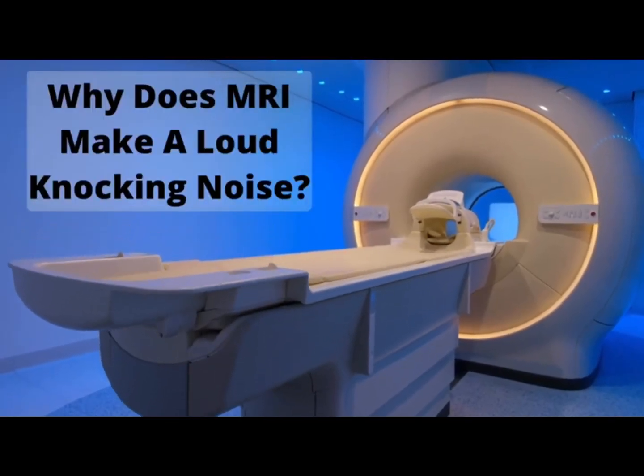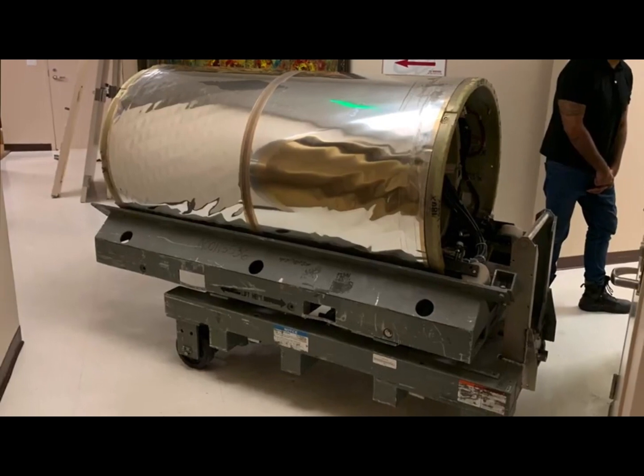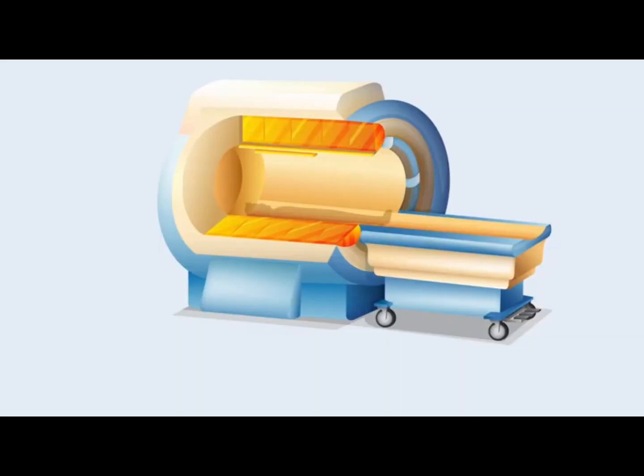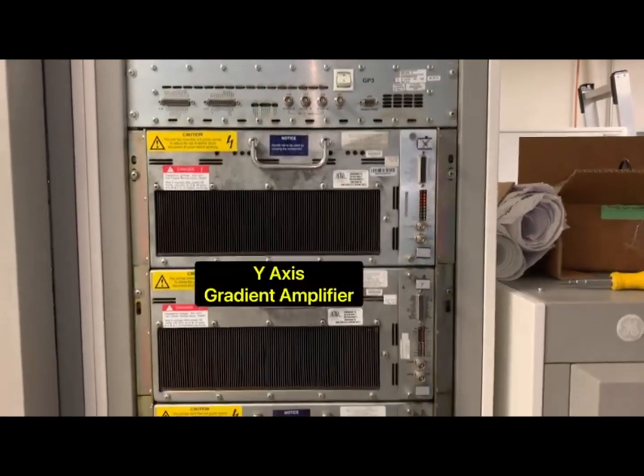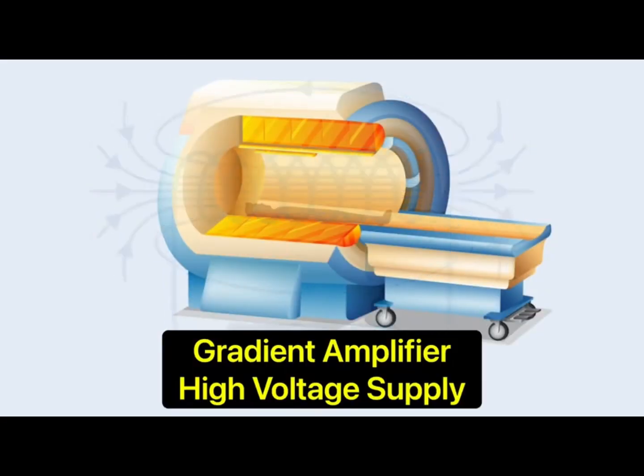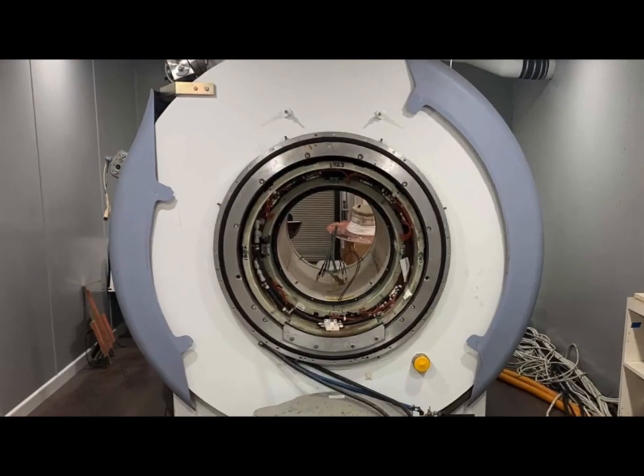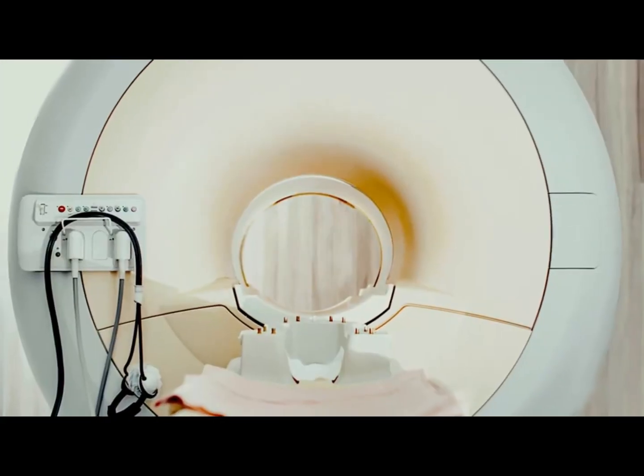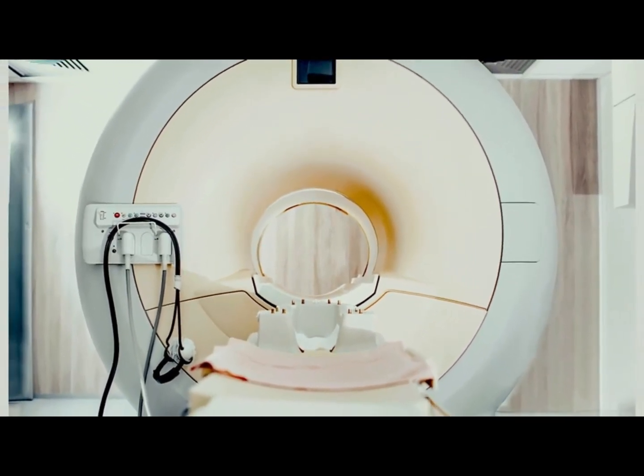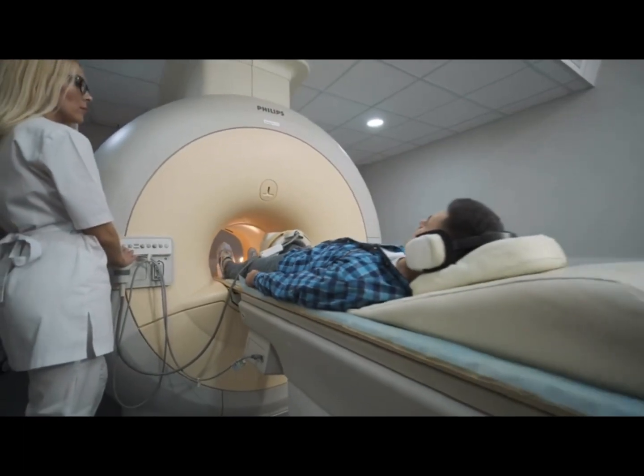The loud knocking noise in MRI scans comes from the gradient coil, which houses three sets of wire coils and produces a strong time-varying secondary magnetic field. Gradient amplifiers supply each axis with rapid pulses of high voltage electricity that contract and expand the coils inside the MRI scanner. The loud knocking noise is the sound of the gradient coils interacting with the primary magnetic field, causing the coils to vibrate against the fiberglass mountings. This can reach noise levels in excess of 100 decibels, so patients must always be outfitted with proper hearing protection.